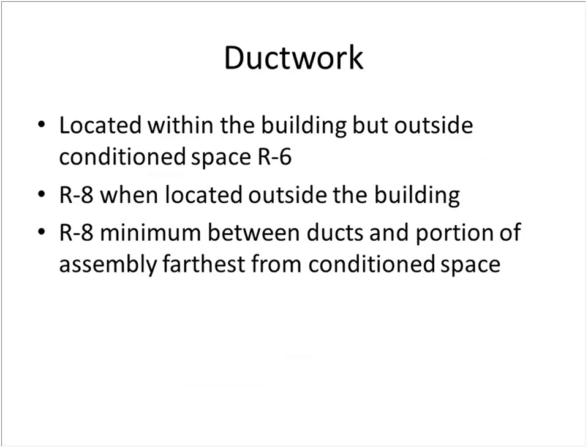Ductwork. These are the requirements for insulation of the ductwork. If it's located within the building but outside conditioned space, it has to be insulated to an R6, and that would be places like unconditioned crawl spaces or in attics, and R8 when it's located outside the building. And that would be a condition like for a rooftop system, and the ductwork were out there. It needs to be an R8.